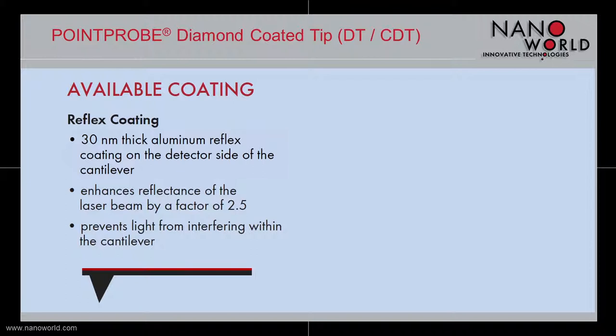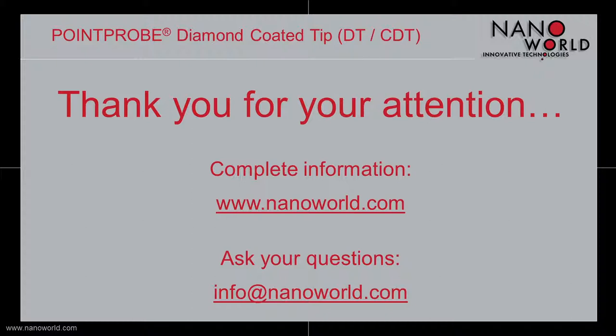All available diamond coated tip probes can be coated with reflex coating on the cantilever's detector side. It consists of a 30 nm thick aluminum layer, which enhances laser beam reflectance by a factor of 2.5 and prevents light from interfering within the cantilever.